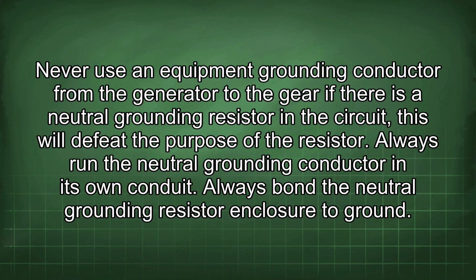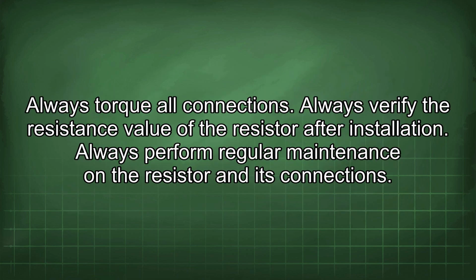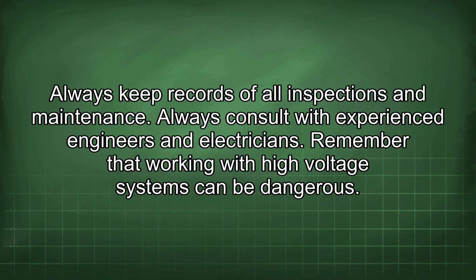Always run the neutral grounding conductor in its own conduit. Always bond the neutral grounding resistor enclosure to ground. Always torque all connections. Always verify the resistance value of the resistor after installation. Always perform regular maintenance on the resistor and its connections. Always keep records of all inspections and maintenance. Always consult with experienced engineers and electricians.